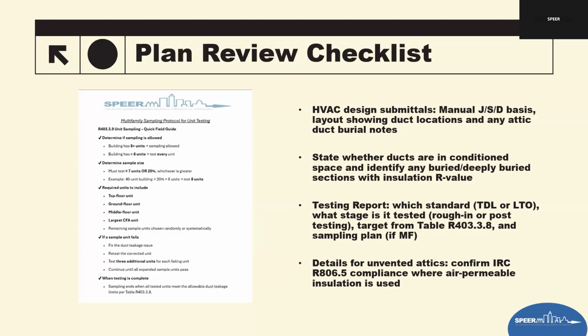Rough-in testing has different leakage thresholds. Sometimes it can. Here lately, now they're all the same. In the older code, it used to be different. Reviewers should also check that the target leakage number from the table, which we just reviewed, 403.3.8, is being met. So is the equipment installed? Is it in conditioned space? How many returns? What's the square footage of the home? This determines whether my duct leakage is going to meet the requirement of the table.